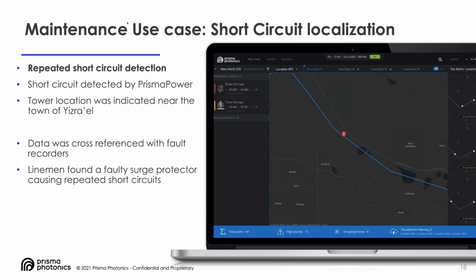Another use case that was tested and demonstrated is short circuit localization. When there is a short circuit event, we can detect it with our system, and what's very interesting is that we can pinpoint the exact tower, not just a range over tens of kilometers. As you can see in the picture, we can give an indication about the event, the time, and the very precise location of the event.